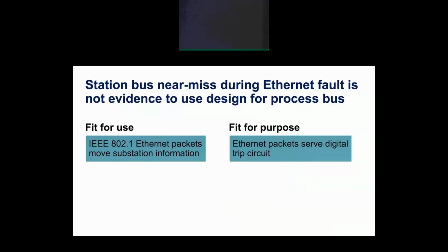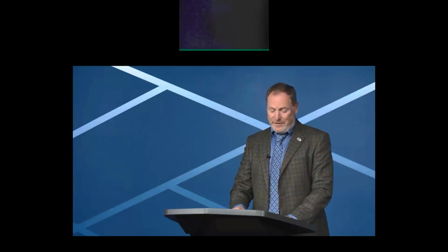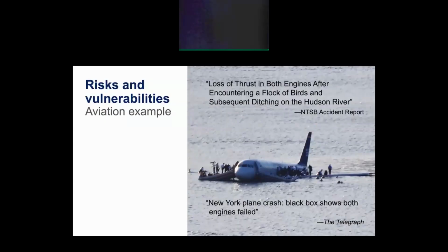A challenge to digital trip circuit design exists when designers make the dangerous assumption that IT and process bus communications require the same level of service. Dunning points out that infrastructure support teams such as IT often confuse fit for use. Yes, I understand Ethernet, which might even be fit for the purpose of business operations. They confuse that with, yes, I understand how to use Ethernet for protection as needed on a process bus communications network. Like the shuttle Columbia near-miss foam strike events, near-miss Ethernet faults and the known unknowns about IT Ethernet systems should cause alarm and not overconfidence.